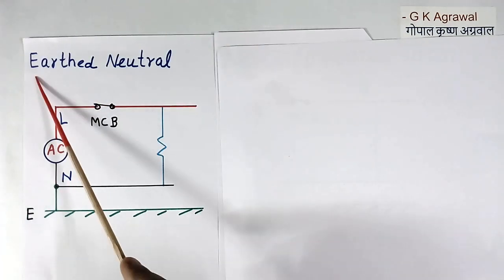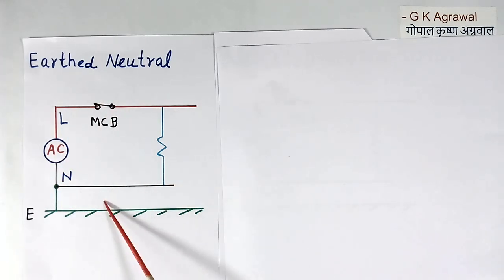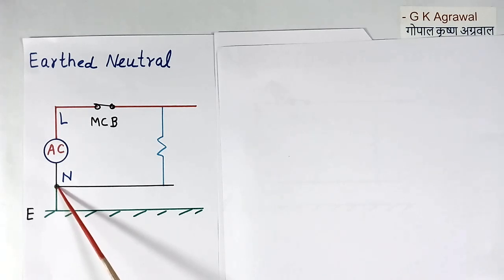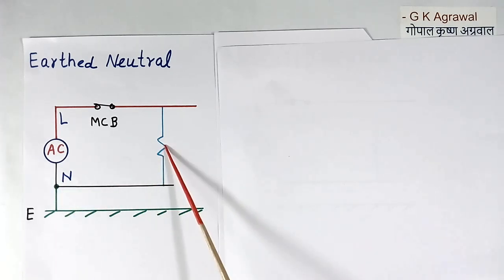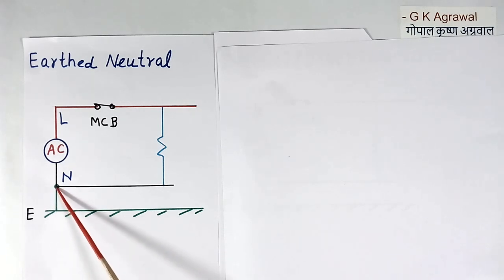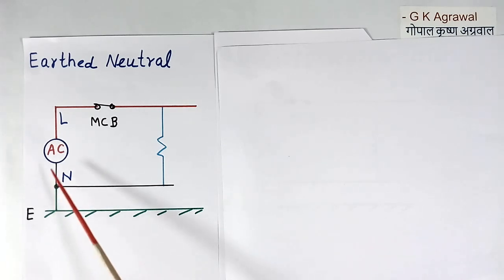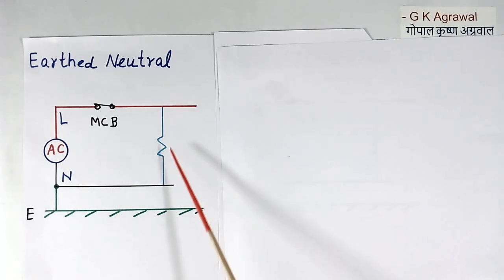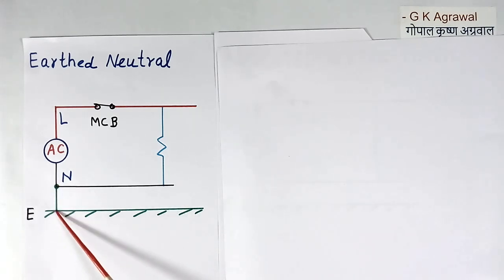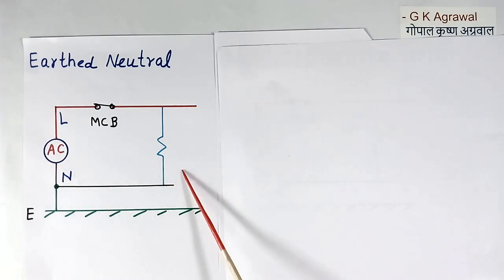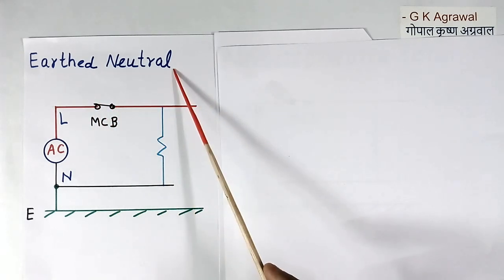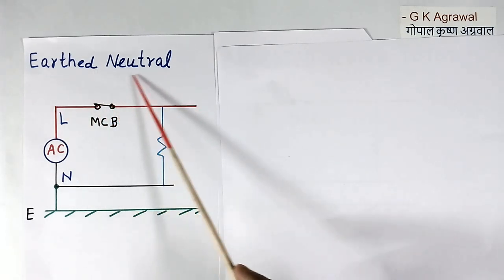I have shown the earth neutral system in this diagram. This is AC supply coming from the substation. This is the load. Here, neutral is connected to earth at the substation. And here we get line, neutral, and earth. Because neutral is connected to earth at the substation, not at the home. So we call it the earth neutral system, or grounded neutral system.